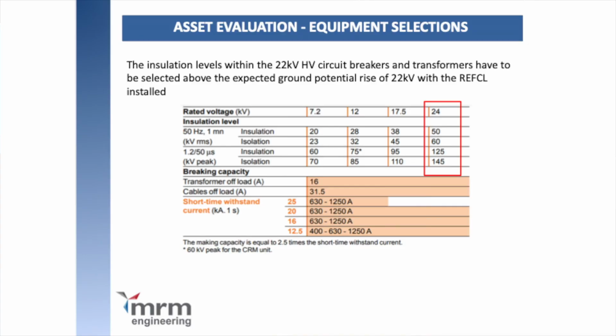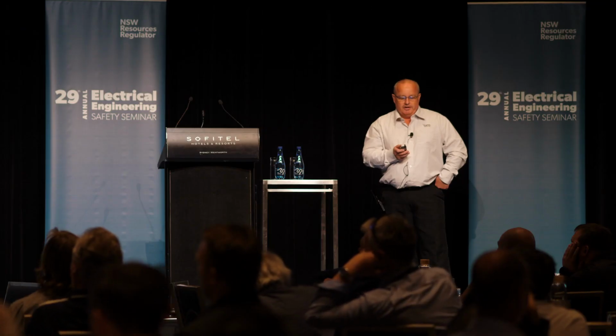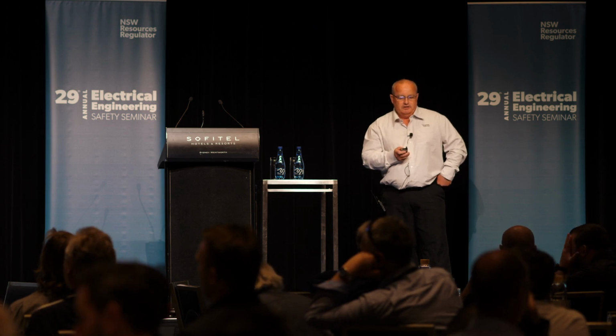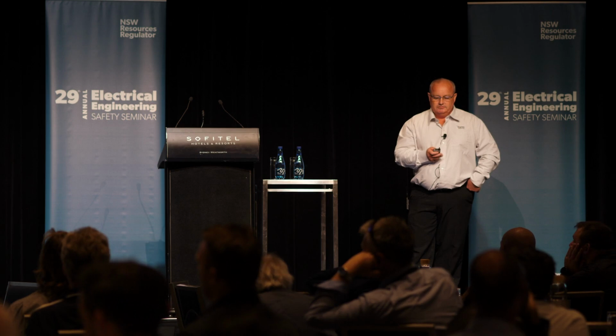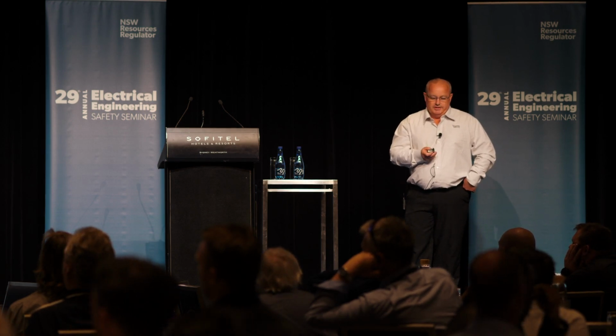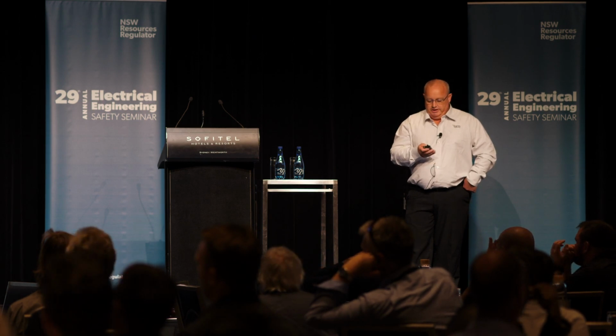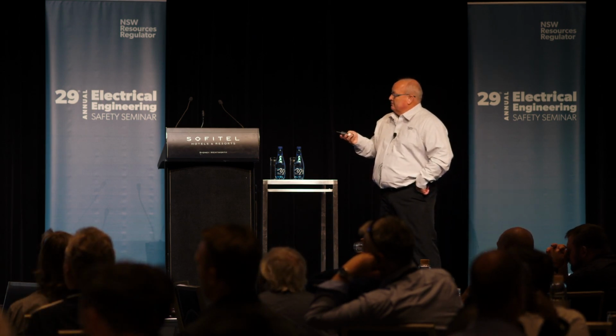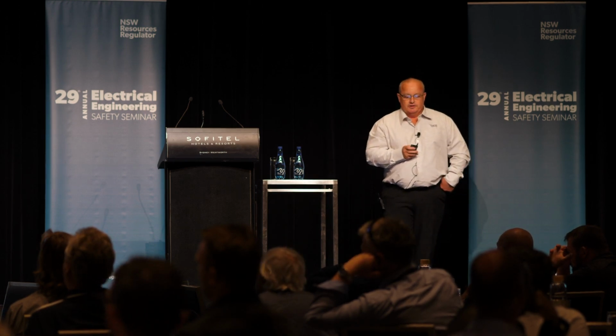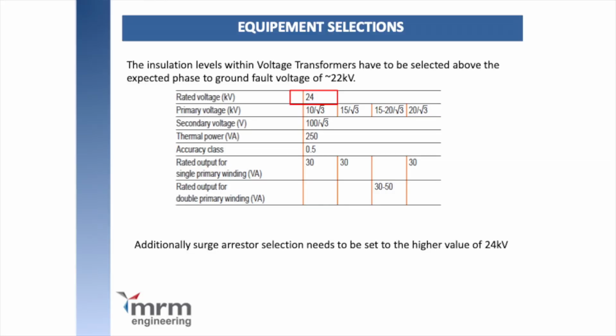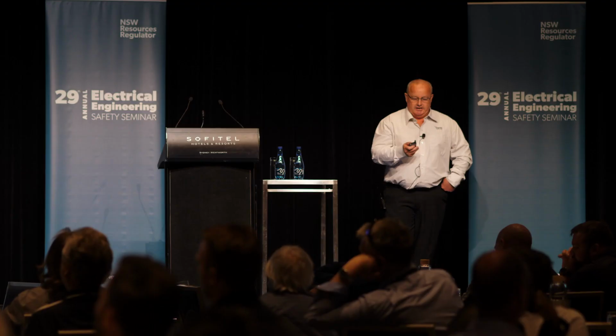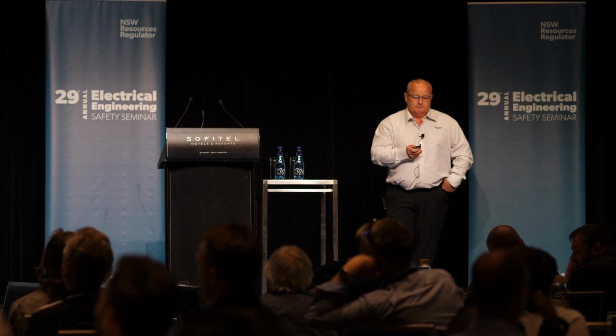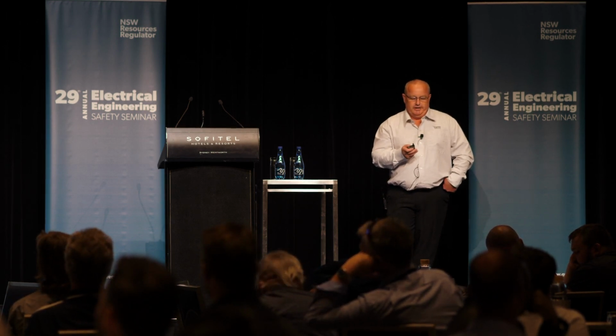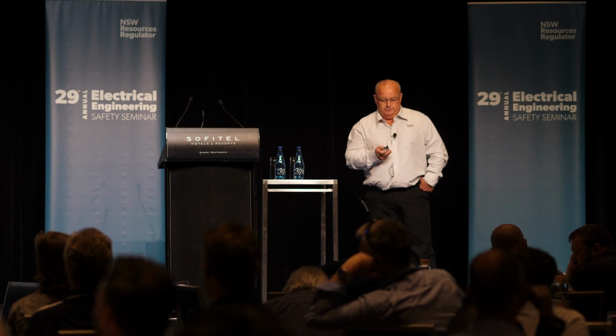So one of the jobs I've been working on, we've been looking at the assets. So when they actually implement this stuff, we've been looking at the installation as far as compliance to now having the phase to earth fault at a higher level. So this particular installation was a Schneider RM6 unit, so it had sufficient clear voltage rating on their VTs so that they were okay. Sorry, that was the CTs. The VTs are fine as well. They've got 24 kV. And additionally, you need to look at your surge arresters. So basically the outcome of the investigations we worked on the RM6 units, it was actually compliant and Schneider actually issued a certificate for it to say that it was all good.